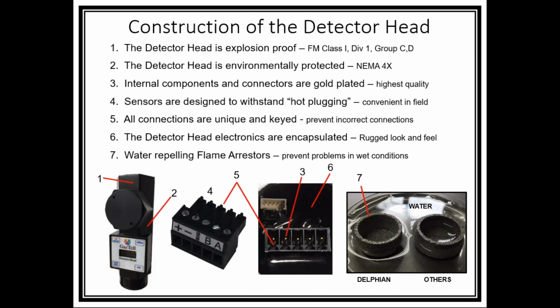Let's talk about the construction of the detector head a little bit. Some of the things that we like to tout is that the detector head is, of course, explosion-proof, FM class 1, Div 1, group C and D, and it's environmentally protected because it's an epoxy. It's actually a powder coating that allows the surface to be coated so that high corrosion materials such as maybe chlorines and other corrosive materials can't get to the aluminum metal. So although it's not stainless steel, it does have a NEMA 4X rating on it.